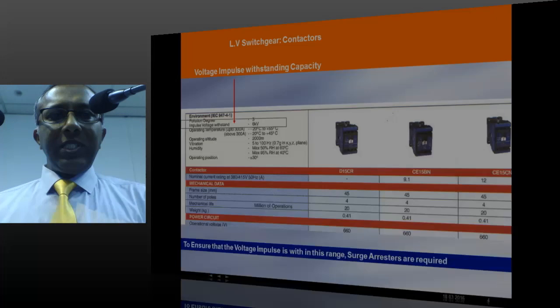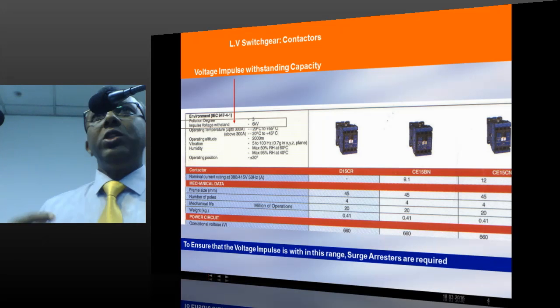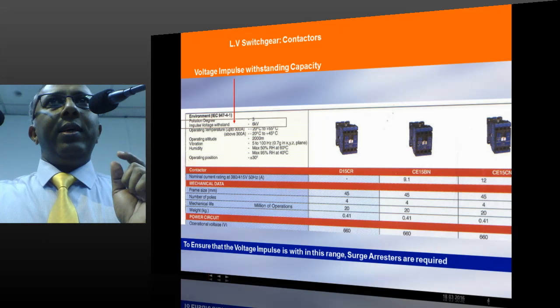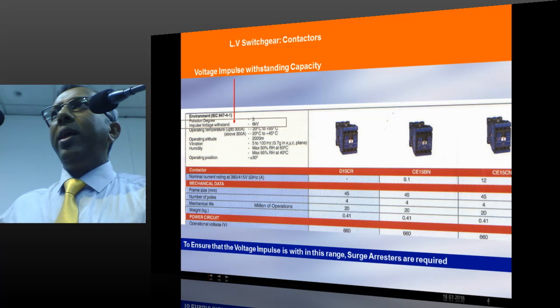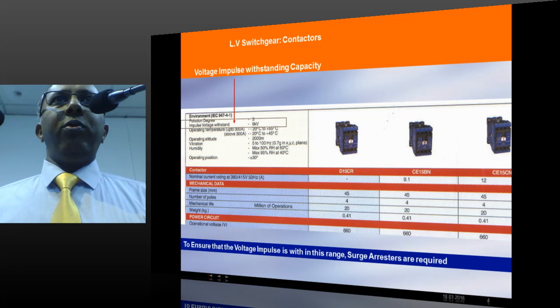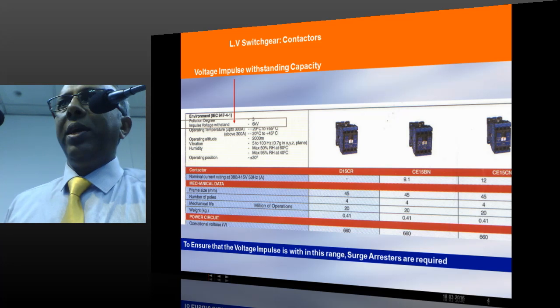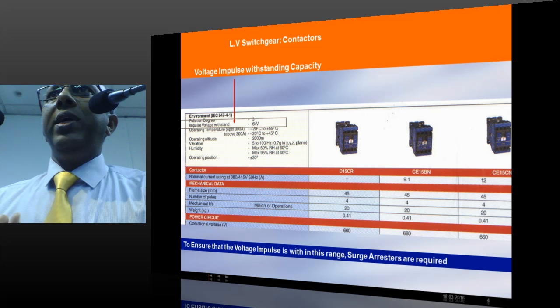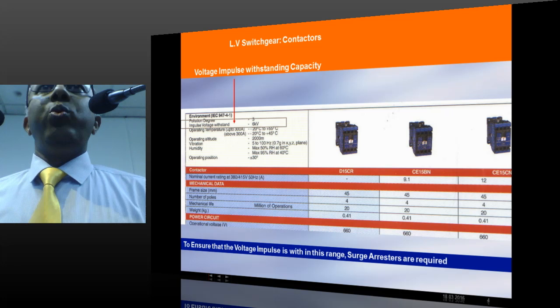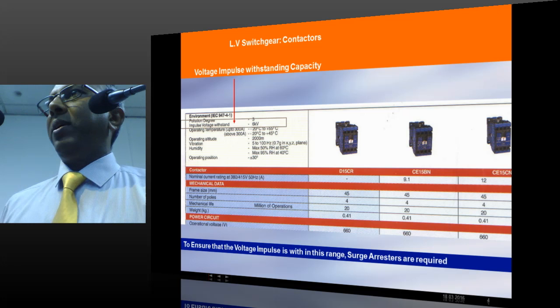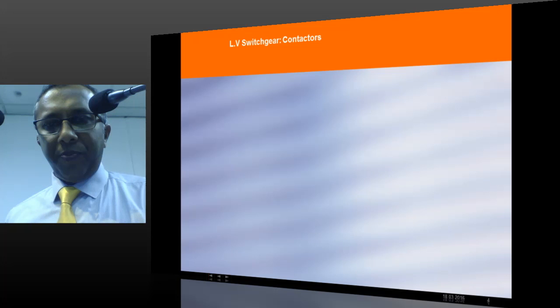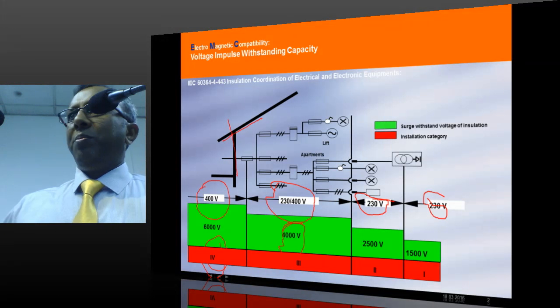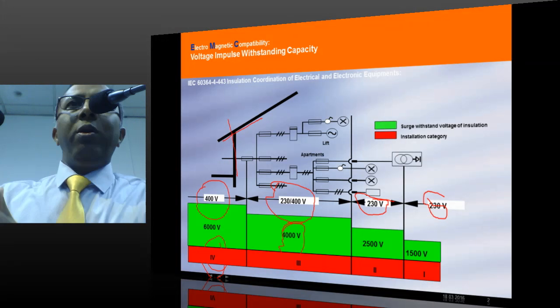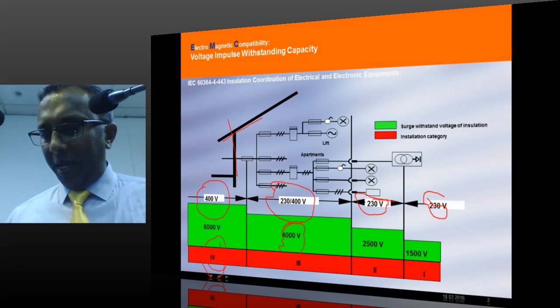So the purpose of showing this particular slide is, once when we design a lightning protection system, finally your electrical equipment is mostly going to be affected due to lightning current flow, and this value is important. That means the voltage impulse withstanding capacity of the equipment has to be known to decide what kind of protection is required for your equipment. Just keep this figure in mind, because at the end of the presentation, this figure will be connected to the lightning protection standard. Then you will be able to understand the purpose of this particular picture.